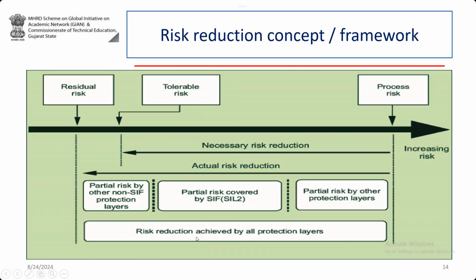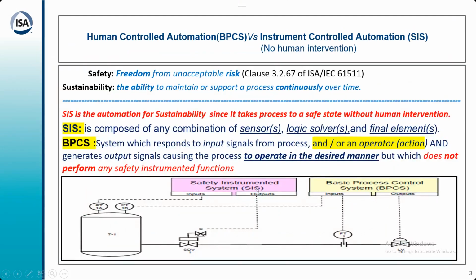BPCS, as I mentioned, is dynamic, whereas the dormant SIS system is passive. It is not dynamic, but it monitors the parameter and takes action when required. So it is passive but dormant. Whether it will take action or not, you will know only when it crosses the set limit. In this case, it is obvious when your control valve is not functioning, you can see it. Here the control valve will remain in the same position. If the safety condition wants it to remain open and close when the parameter exceeds, this will remain open. And if the control valve remains open for a long period, it may get stuck.